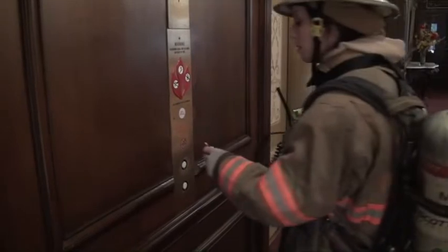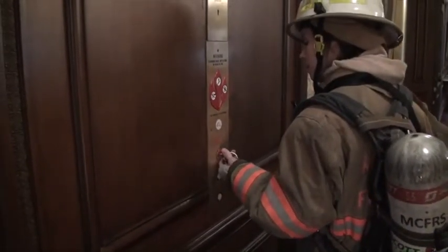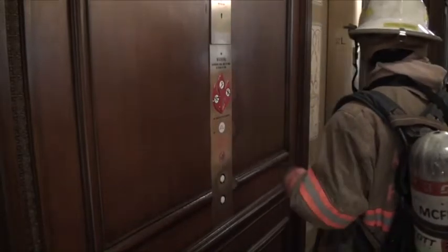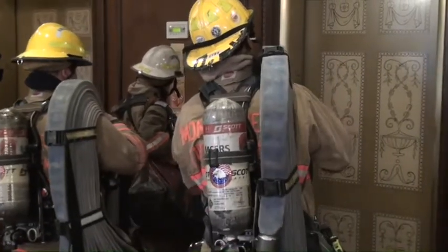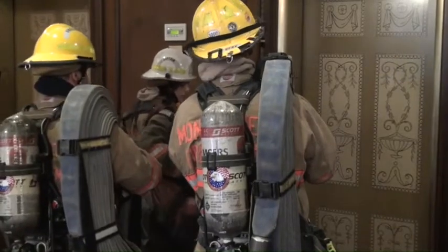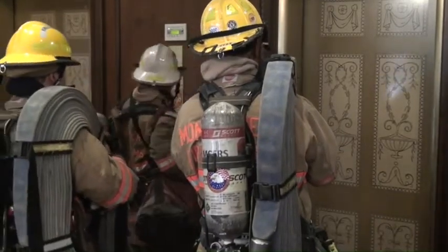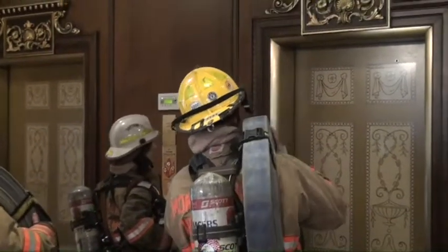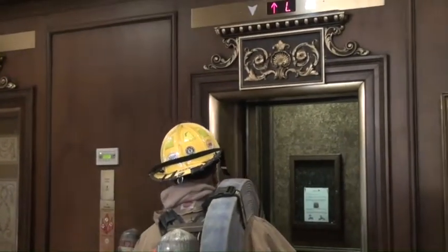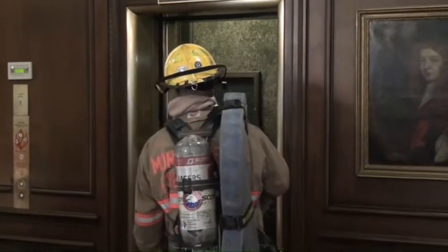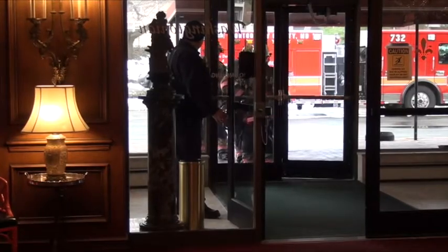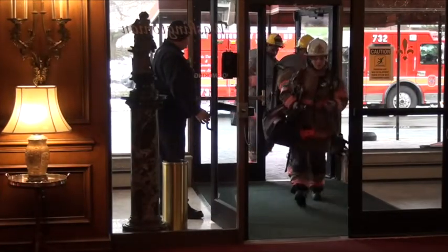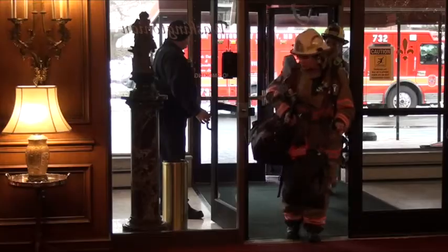Phase 1 of the fire service elevator control allows emergency responders to gain control of the elevator cars within the elevator bank or multiple cars in one location and safely override the elevator occupant's controls. This override will recall or return the elevator car to a predetermined floor in the building. This override will not allow the elevator car to be called up to the fire floor. The predetermined level is usually the lobby or main entrance where emergency personnel most likely will enter the building.